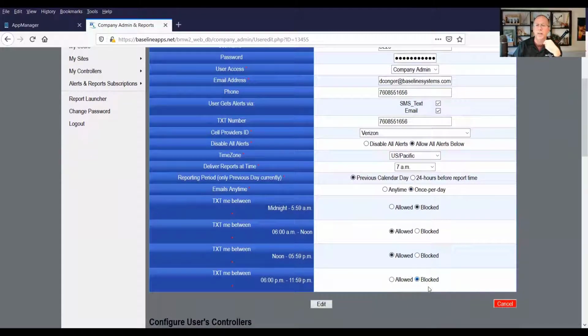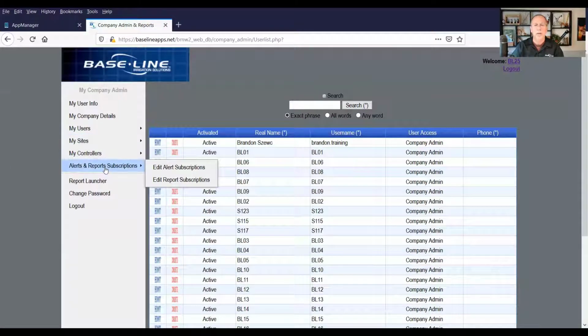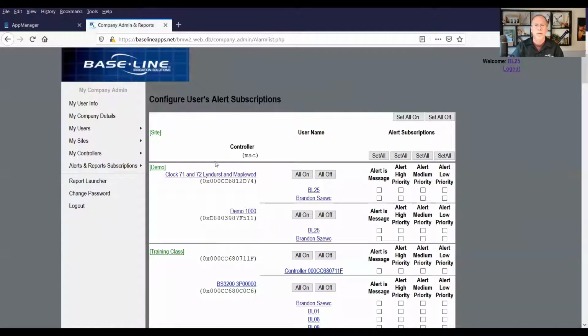I can also select the time of day that I'm going to allow the alert. If I didn't allow them at all, or if I only allow them at certain times of day, it might determine when I get my alert. The other thing to look at is the alert subscription. So I'm going to go to alerts and report subscriptions and open up just alert subscriptions. This is going to decide for this particular controller, do I want all alerts on or all alerts off? Well, none of them are on, so I definitely want to turn them all on. Now every single alert will come through. If you decide later on that you're getting too many alerts, you might turn off the low level or low priority alerts. I'd recommend starting with all the alerts on because you don't want to miss out on some that may be high level to you, but low level to our engineers when they set that up.